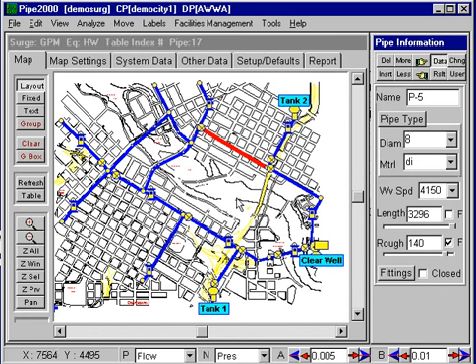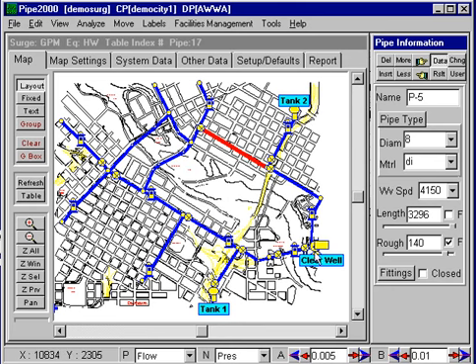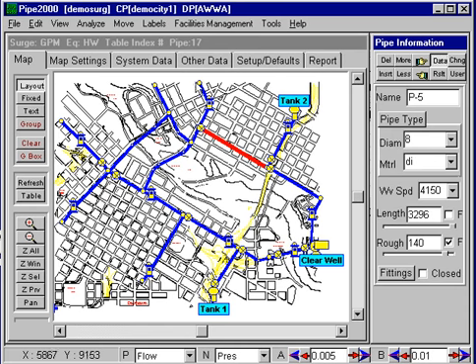The additional data required is data to describe the shutdown of the pump, which is what is causing the transient. In this problem we are going to shut the pump down, going from the situation where the pump and the tanks are supplying the system to just where the tanks are. We know that when we did this earlier in the regular simulation there was just a small change in pressure — a slight drop in pressure throughout the system. Now we'll see what the transient is between the two conditions.